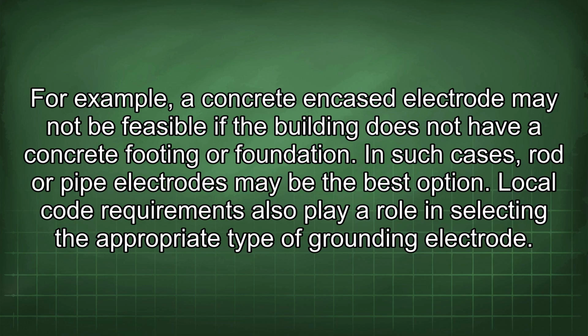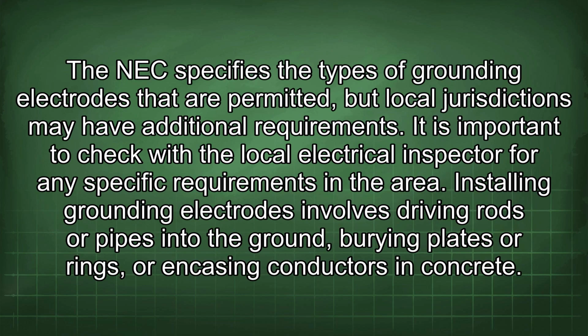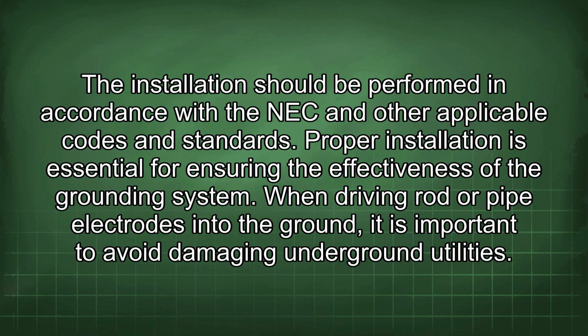Local code requirements also play a role in selecting the appropriate type of grounding electrode. The NEC specifies the types of grounding electrodes that are permitted, but local jurisdictions may have additional requirements. It is important to check with the local electrical inspector for any specific requirements in the area. Installing grounding electrodes involves driving rods or pipes into the ground, burying plates or rings, or encasing conductors in concrete. The installation should be performed in accordance with the NEC and other applicable codes and standards. Proper installation is essential for ensuring the effectiveness of the grounding system.